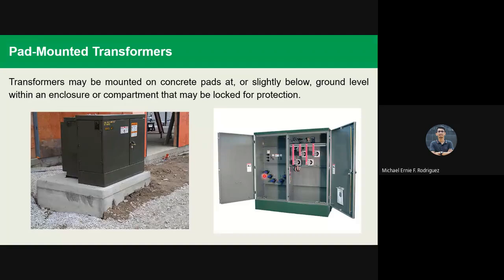These are energized, remember, since this is in service. So opening it is dangerous. The terminals may be mounted behind an insulating barrier, so you just have a barrier, and your connections from the cables are made through bayonet type connections, on insulated elbows which are plugged through these jacks to the terminals here. These units are called dead front units, and they provide an additional margin of safety. So those are your pad-mounted transformers.